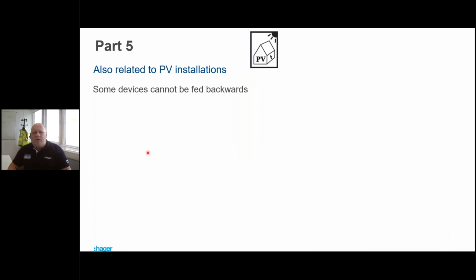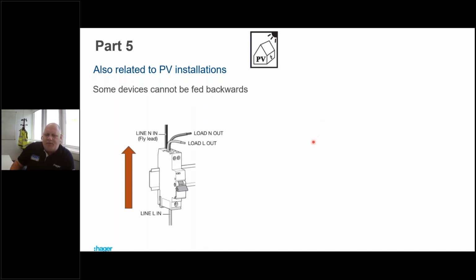Part 5. Some devices can't be fed backwards. What does that mean to us? When we've got an RCBO, it sits on a DIN rail and we feed the power into the bottom of it where it says line in. That would generally be a bus bar. Neutral flying lead, that's fixed, so that goes into our neutral connector. And then we take our load out of the top here.